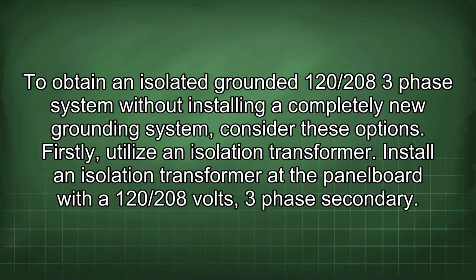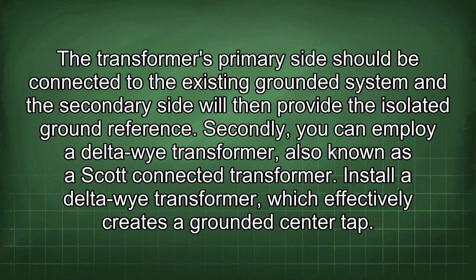To obtain an isolated grounded 120/208 three-phase system without installing a completely new grounding system, consider these options. Firstly, utilize an isolation transformer. Install an isolation transformer at the panel board with a 120/208 volts three-phase secondary. The transformer's primary side should be connected to the existing grounded system, and the secondary side will then provide the isolated ground reference.